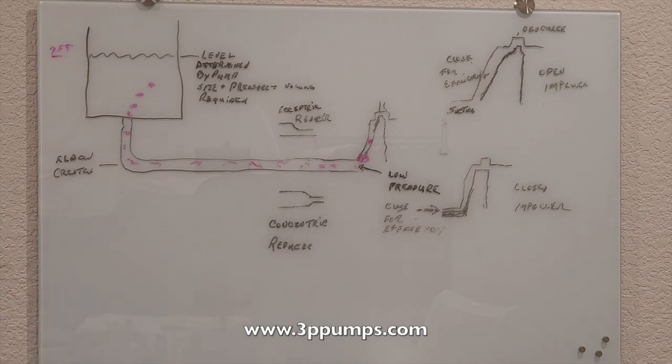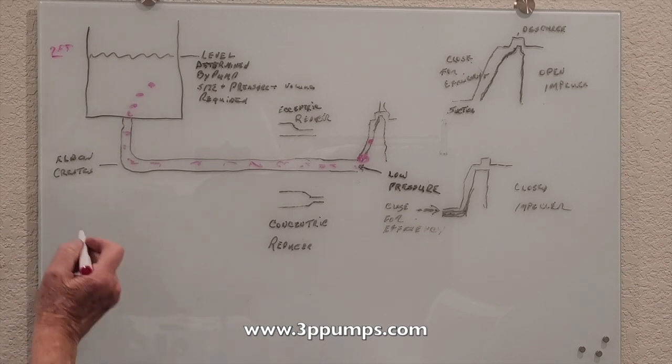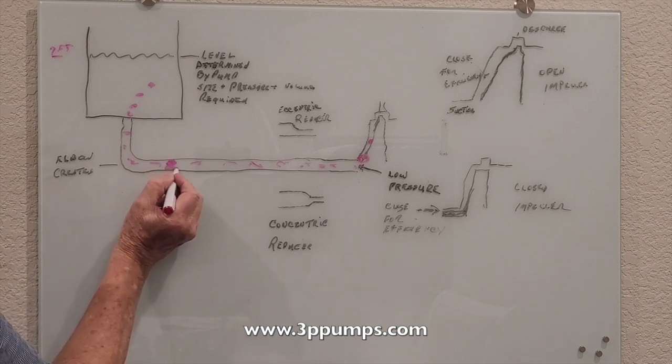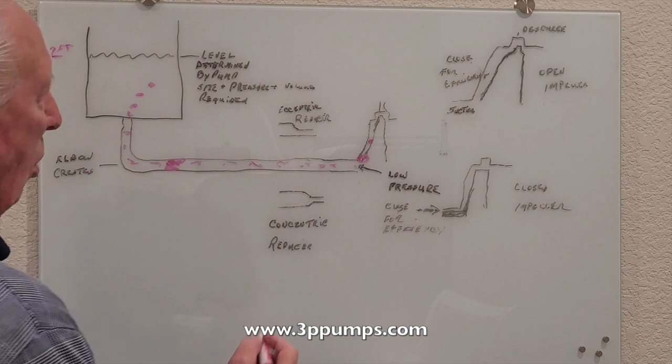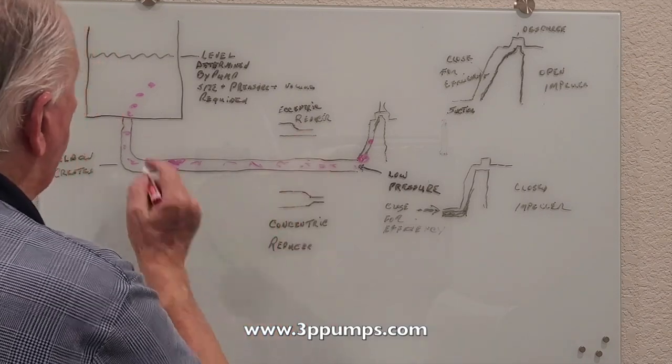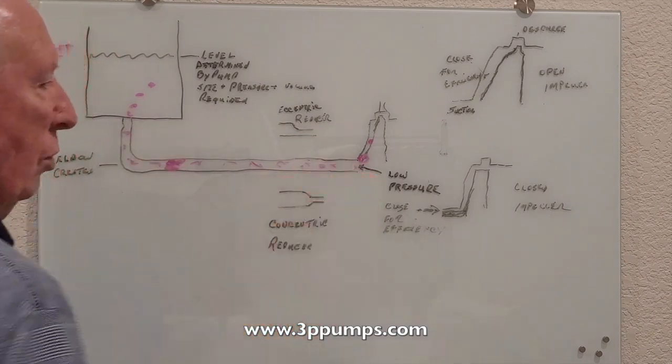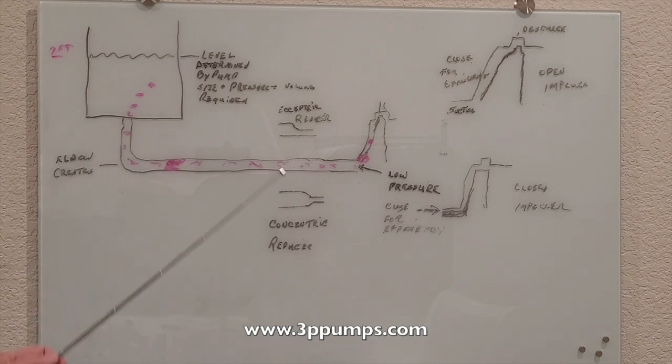Now let's go through some other problems that might cause cavitation. We get into a stoppage in your pipe in here. Let's say something's got it all stopped up right in here. It's going to cause you the same problem because you're not getting this pressure from here to here because you're getting a clog right here, okay? The other thing that can cause you problems is a reducer. If you've got a 3-inch pipe and it's going into a 2-inch section here, you try to reduce it down.